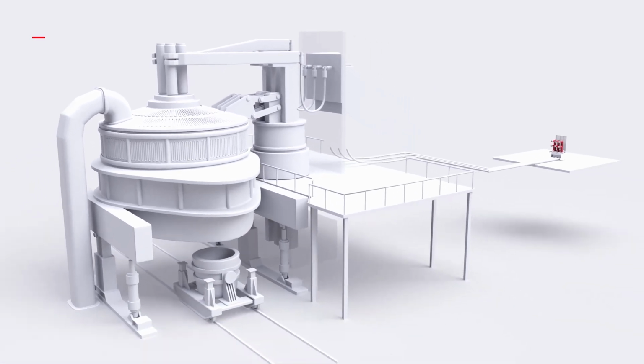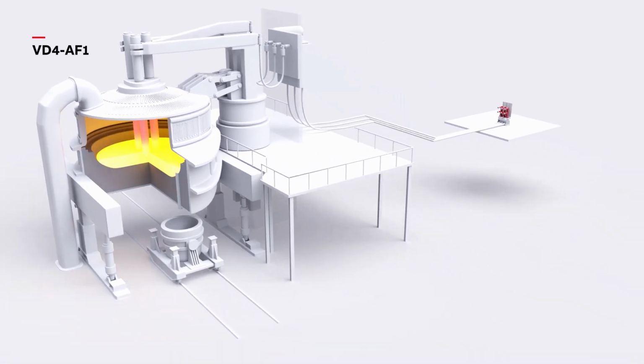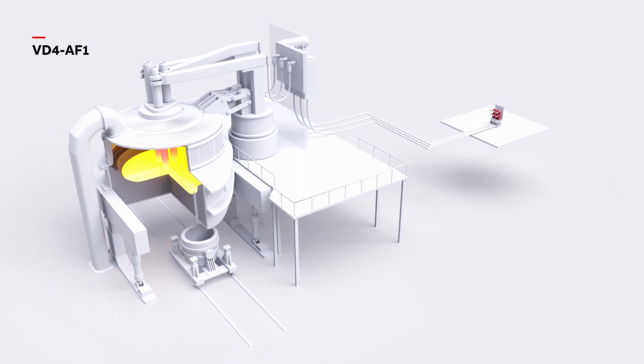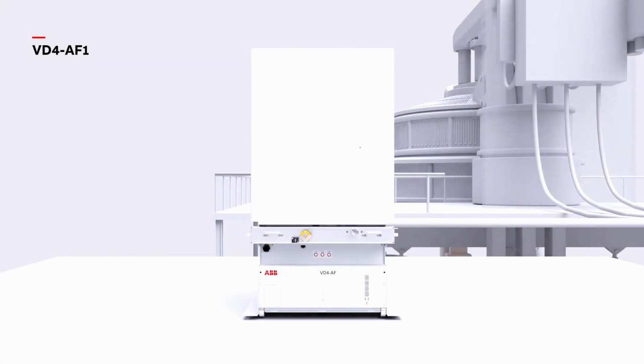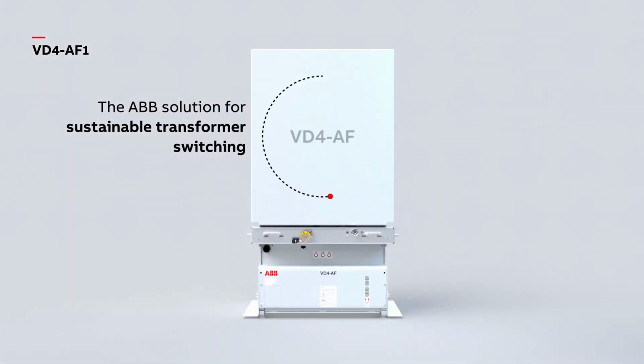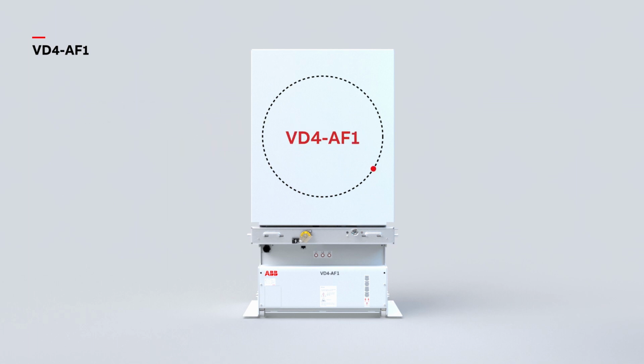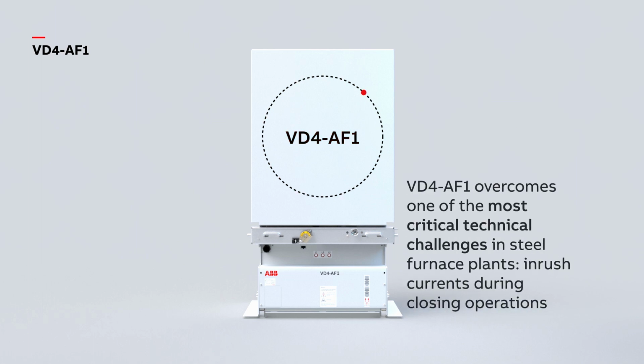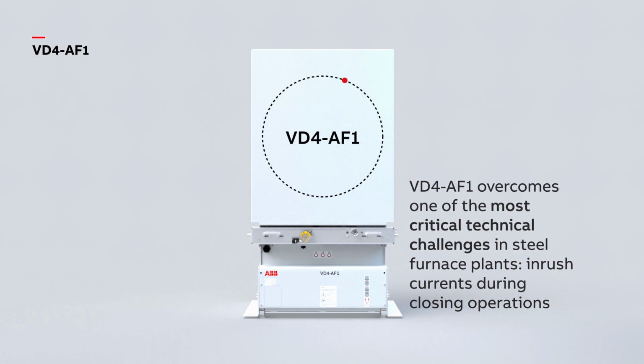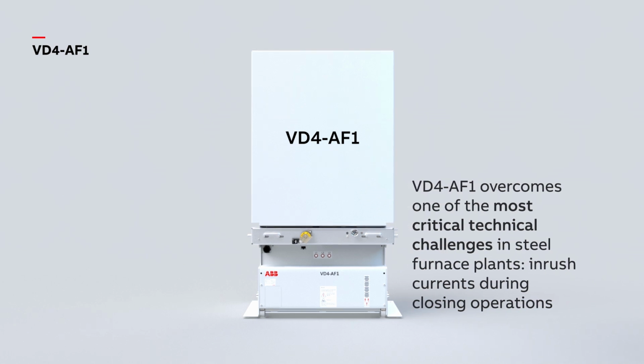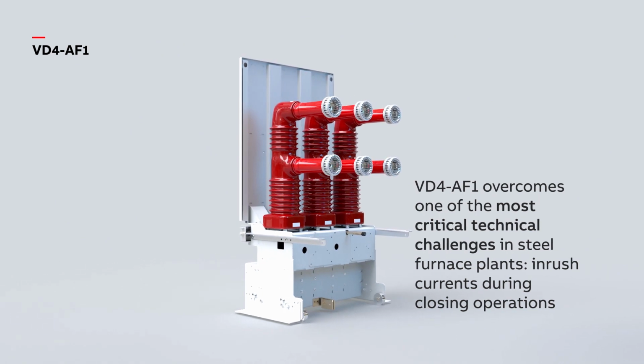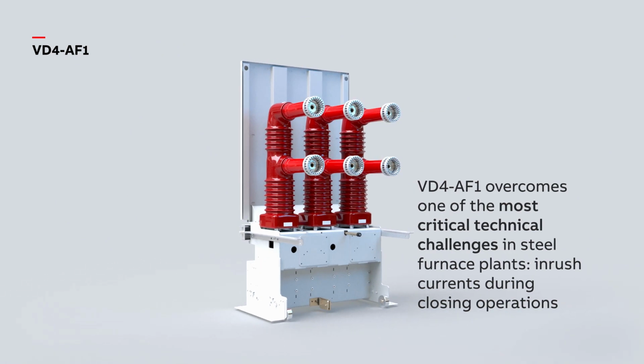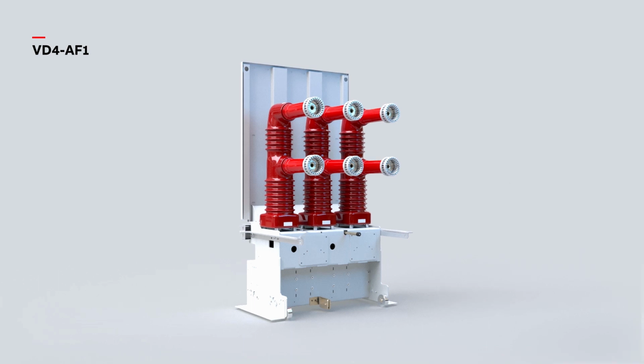The ABB VD4-AF1 circuit breaker takes the performance of the VD4-AF and pushes it to a higher level, answering current environmental awareness. After the release of the VD4-AF, being the ABB solution to protect steel furnace operations, the VD4-AF1 takes a step ahead in answering the customer's need of overcoming the most critical technical challenges: the impact of inrush current on the health of medium voltage transformers.